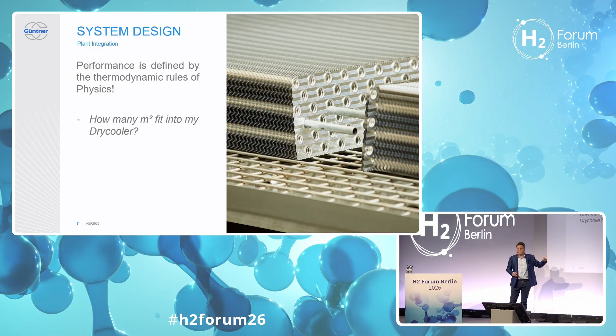Once we know this, we also know how many dry coolers we need, and it's more than just one dry cooler on top of a container. To give you a rough idea, a 50 megawatt electrolyzer plant needs between 24 to 30 megawatt of cooling capacity. Sounds like a lot, that's the energy that needs to be dissipated.